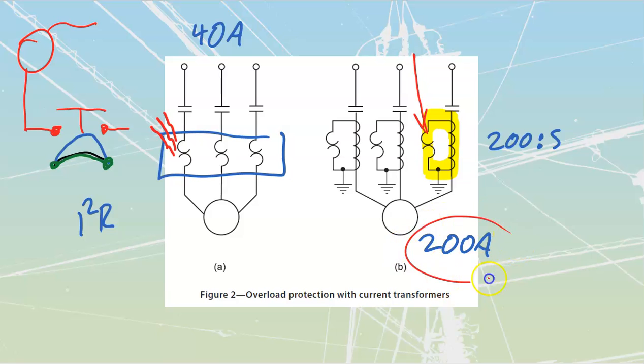If I'm monitoring a 200 amp motor over here, all I would need to do is have a CT set up that's a 200 to 5, and then I can go and place a 5 amp heater. That's going to be a tiny little heater, and it's going to be really small, compact, and easy for me to go and monitor. So that's what we're doing inside of all of these systems over here. Very common way that we're just going to go and jump it down.